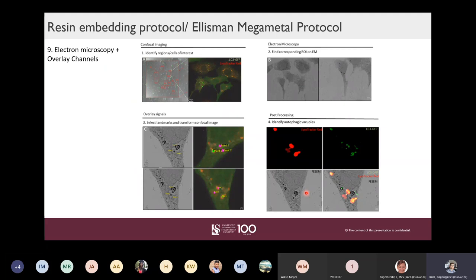Ultra-microtome sectioning is quite intensive on its own. The sample is sectioned with a diamond knife — this is also referred to as ultramicrotomy. Sections go down to about 70 nanometers in slice width. The sections are caught onto a water reservoir and scooped up onto thin grids or silicon nanowafers for placement in the EM sample holder. If something goes wrong with sectioning, your samples are essentially done for. We cut the block in a trapezoid shape to help with orientation.